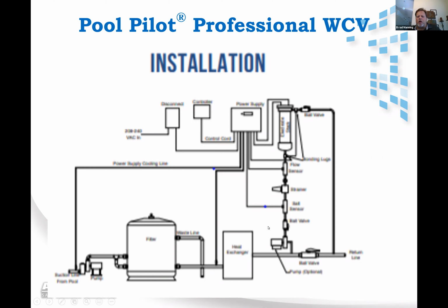On this side, you've got your other plumbing. You've got basically a booster pump, same as what you'd use on some of the vacuum systems out there. But you have a booster pump that's going to take water from the return line here, push it up through the system. It's going to run through the salt sensor. It's going to run through this valve, run up through the flow sensor, and then into the cell. And then it's going to come back down and return downstream of a ball valve. You have to have a ball valve or check valve in here to make sure you're diverting water up into the manifold. If I'm not mistaken, we have a lease and rental program on that as well.